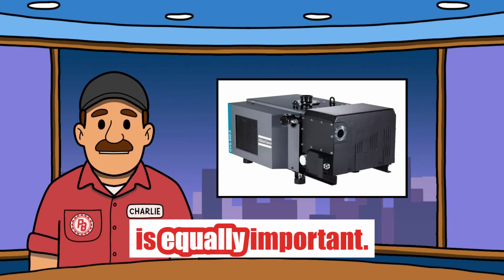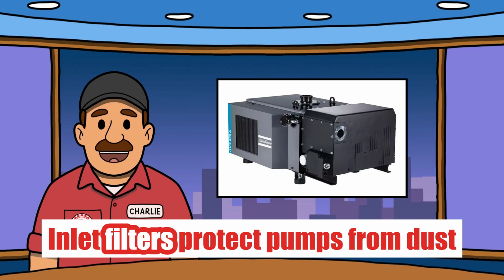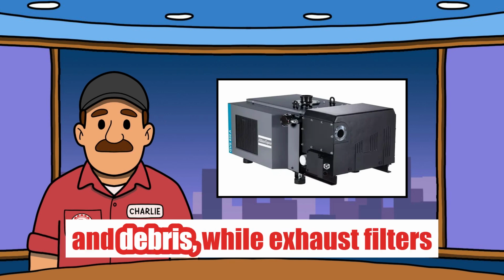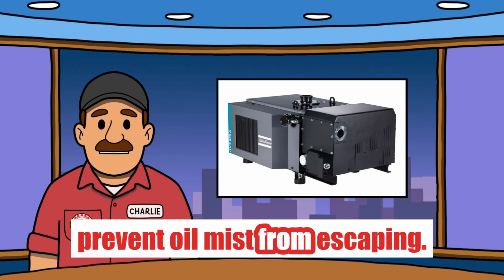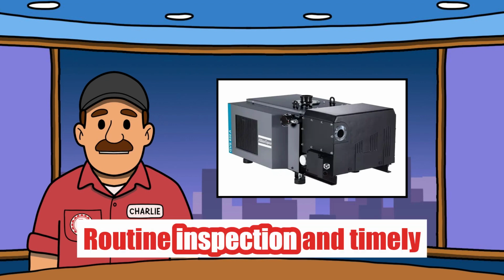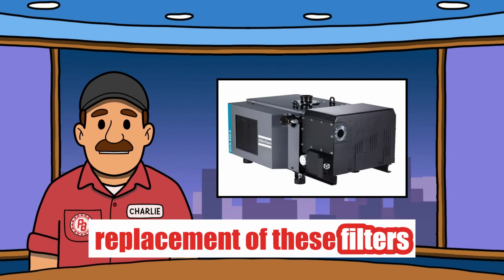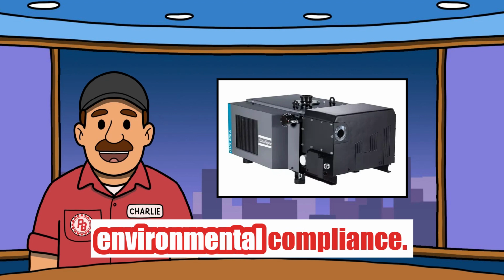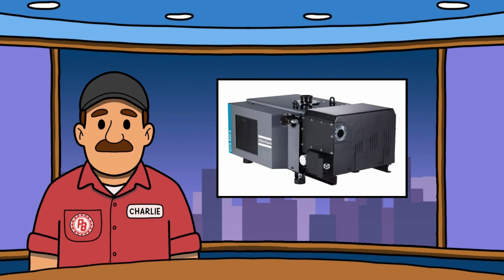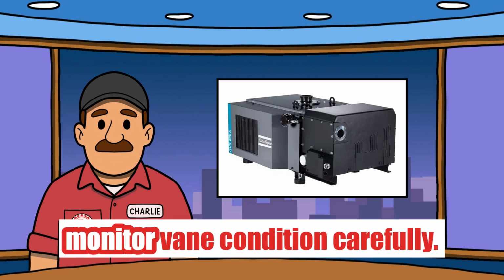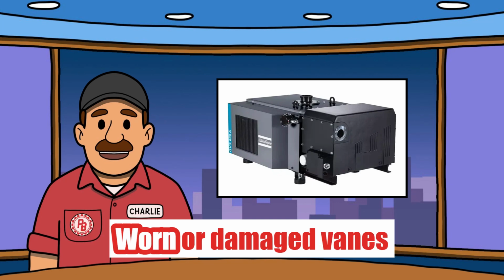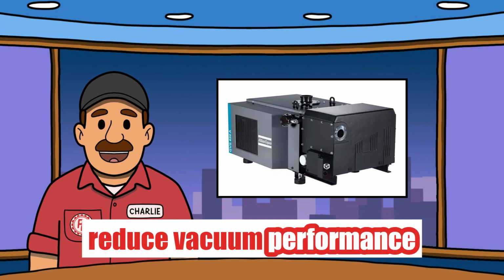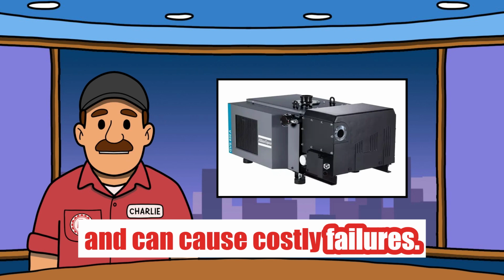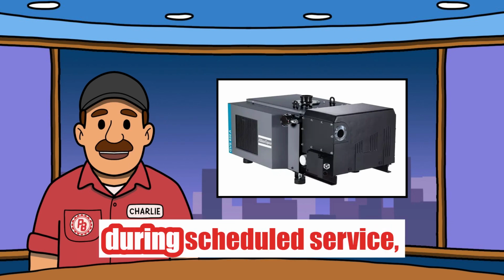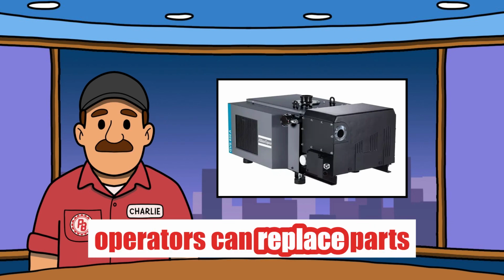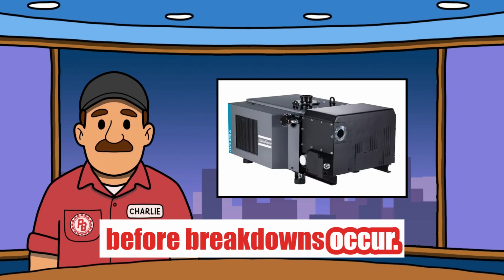Filter replacement is equally important. Inlet filters protect pumps from dust and debris, while exhaust filters prevent oil mist from escaping. Routine inspection and timely replacement of these filters help maintain efficiency and environmental compliance. Technicians are also advised to monitor vane condition carefully. Worn or damaged vanes reduce vacuum performance and can cause costly failures. By checking vane wear during scheduled service, operators can replace parts before breakdowns occur.